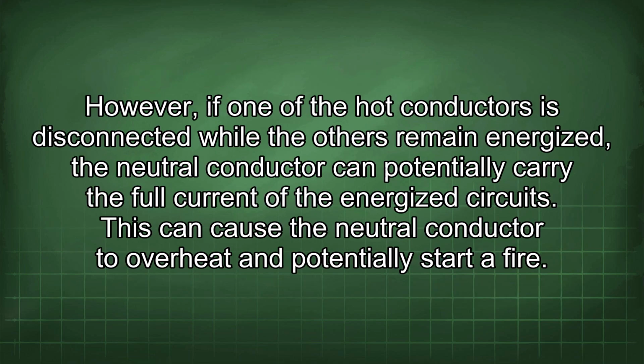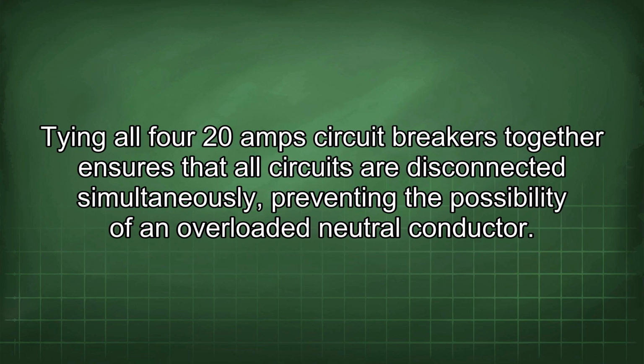However, if one of the hot conductors is disconnected while the others remain energized, the neutral conductor can potentially carry the full current of the energized circuits. This can cause the neutral conductor to overheat and potentially start a fire.